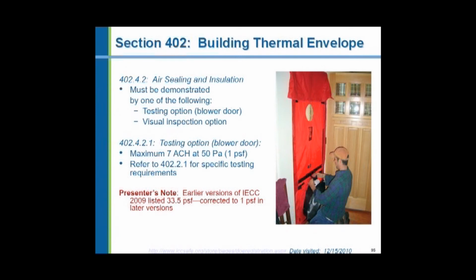The inspector may tell you to employ someone, a certifier, to do this and certify that your house is sealed up tight. But another method, a blower door method, is done after the house is completed, and it is the proof of the pudding, so to speak. It demonstrates the actual leakage rate of the house as it was constructed. And the blower door is basically an extending aluminum frame. It telescopes to stretch a canvas panel across an outside door. And you'll notice that here's the door. It's been opened. The residential door is open to the interior.